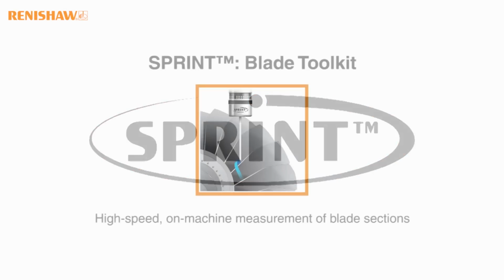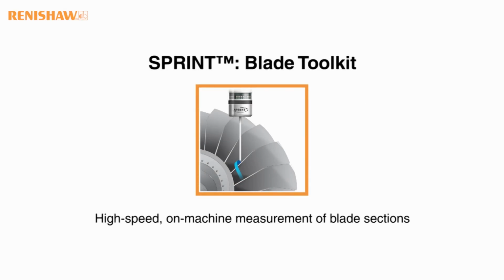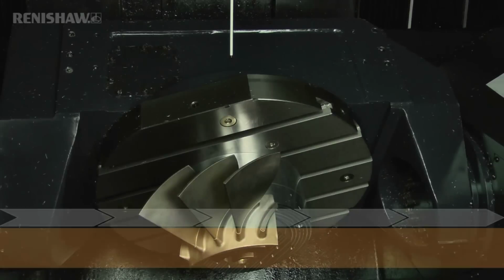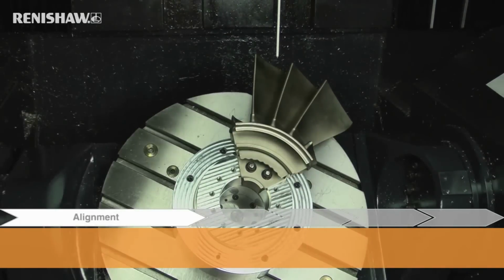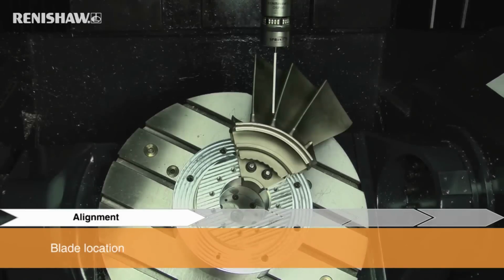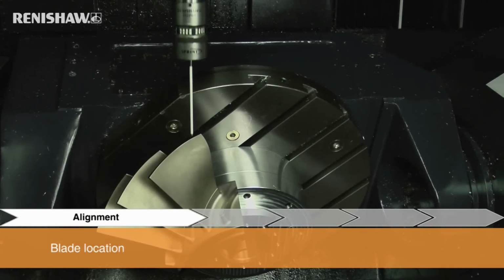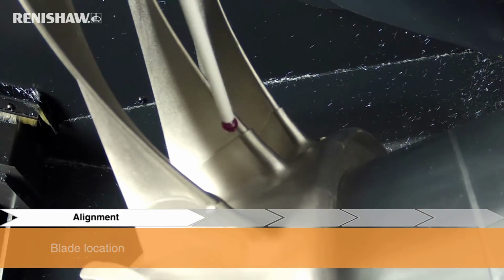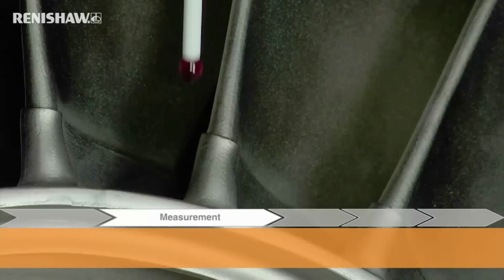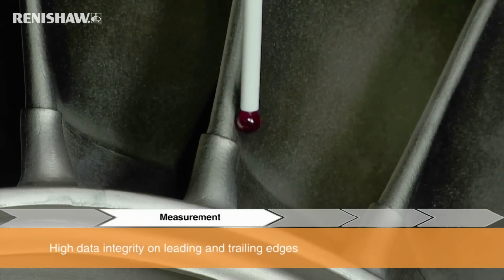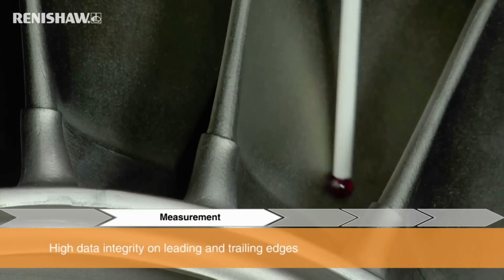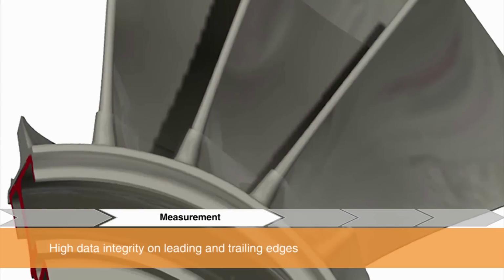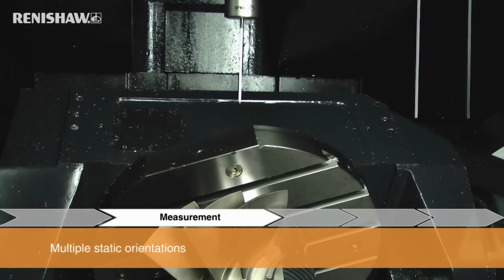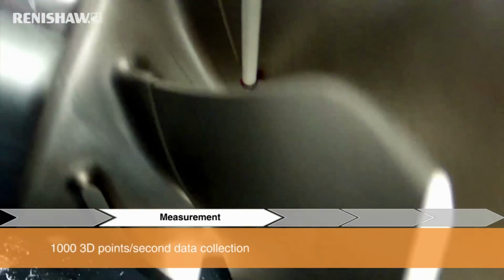Here's some video of the toolkit in action. It goes through a series of stages and steps and tasks. We first carry out a procedure to locate the blade and align it by locating the edges, the so-called edge find, to align the blade and orientate it. We then measure the blade in 4 static orientations, so the 2 faces and the leading and the trailing edge. We take a number of sections which are predefined, or you can define the number of sections that you wish to measure. Again, collecting a lot of data.